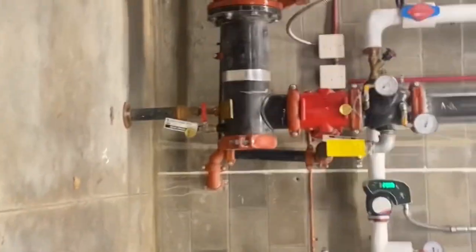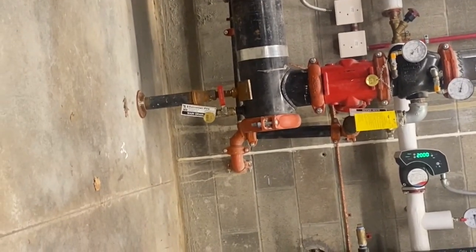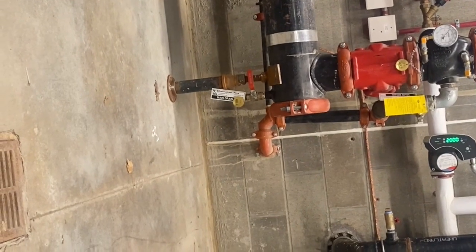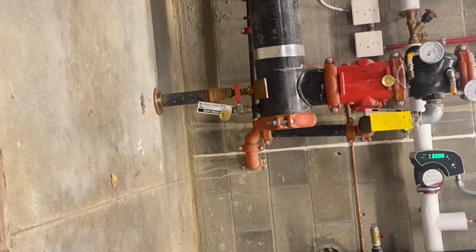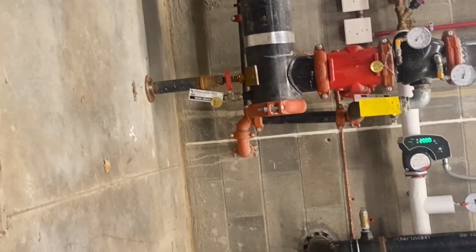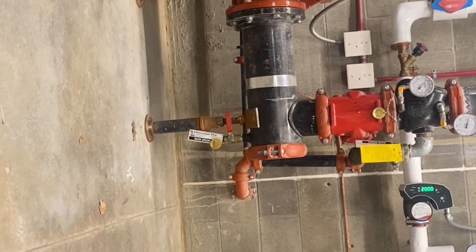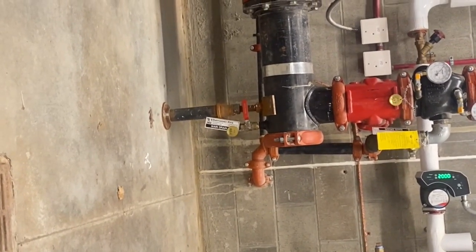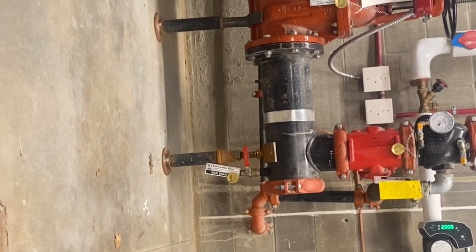And so the steam comes in, and it might hit an exchanger that changes it to hot water. But in that exchanger too, they will run tubes of condensate, or they will run domestic water through it, but it's a separate feed, right? So you never intermix them. Usually there's a hot water heat exchanger and a domestic hot water exchanger, and you never even intermix the two.